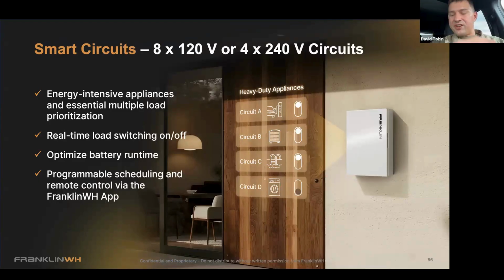This also integrates -- if you have our smart circuit module and multiple aHubs, up to 4, these will all show up under the customer's smart circuit. So they can set functionality times, SOC settings. If you're ever off grid and you hit like 60% and you think you no longer need this load, you can have the system automatically turn that off. That way, if you have a longer outage than anticipated, the system will automatically protect you without you having to wake up in the middle of the night, check your SOC, and worry that you won't make it all the way through -- especially if you have other devices in your house that need to run, like a fridge, freezer, or any sort of medical equipment. The system will automatically take care of that for you.